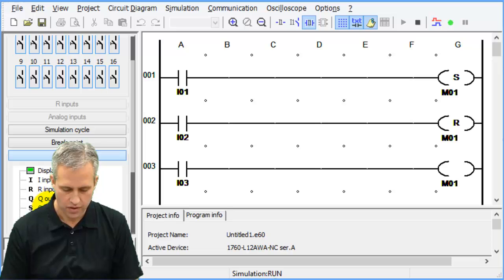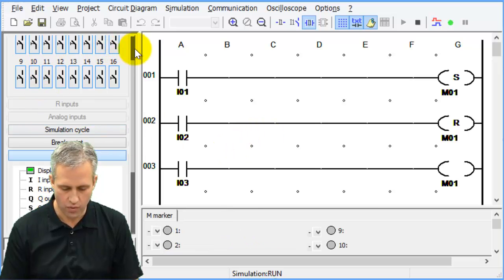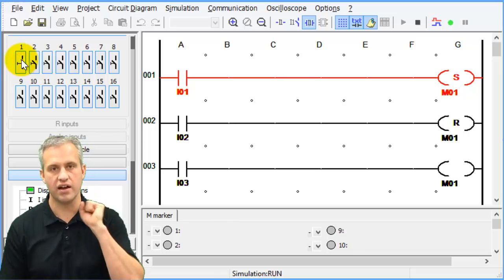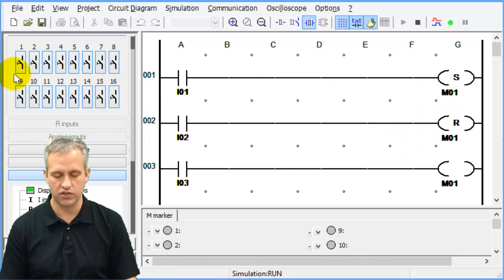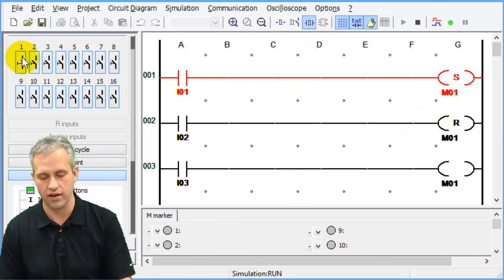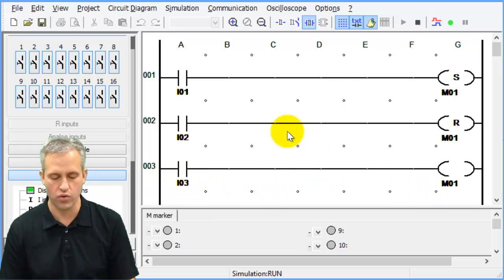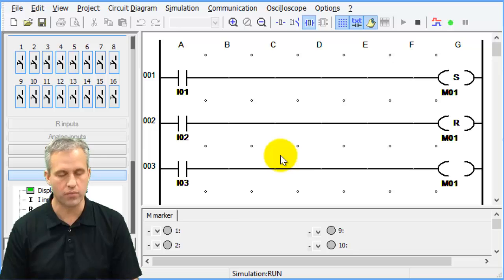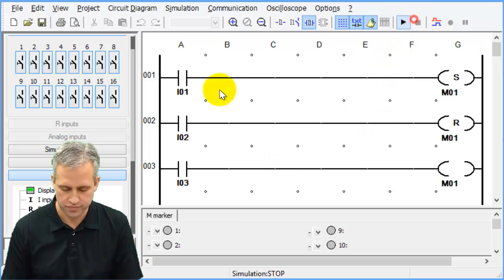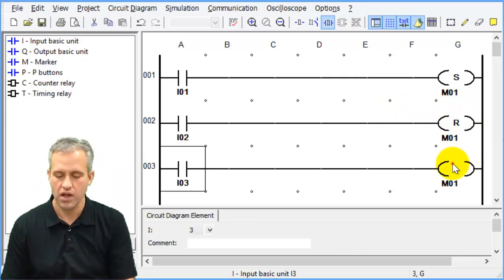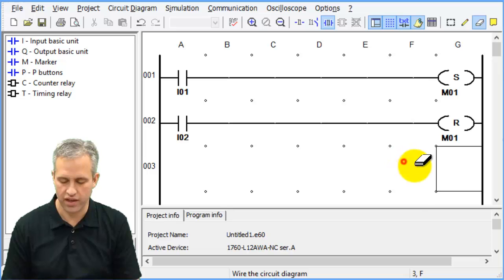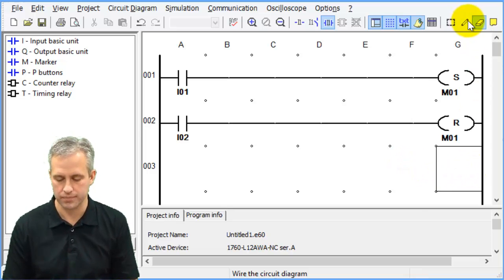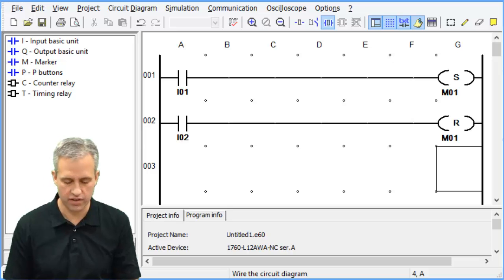Here I'm going to have I3 control marker one as well with a contactor. This is a disaster — I've got a set and reset controlling this marker but also a contactor. Contactors are very different because they're telling you what to do all the time. If I hit I1, it's trying to set the marker high, but rung three is telling it to go low. You've got two things controlling marker one. It's fine to have multiple sets and resets, but if you ever have a contactor, it must be the only thing controlling that marker or output.